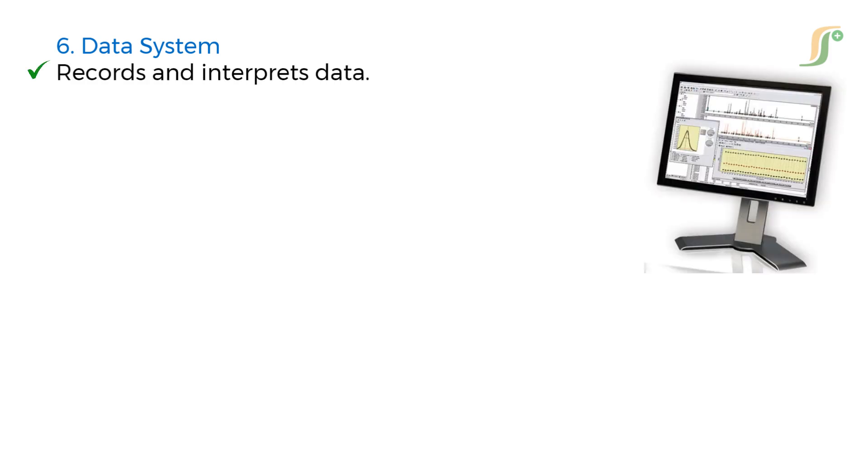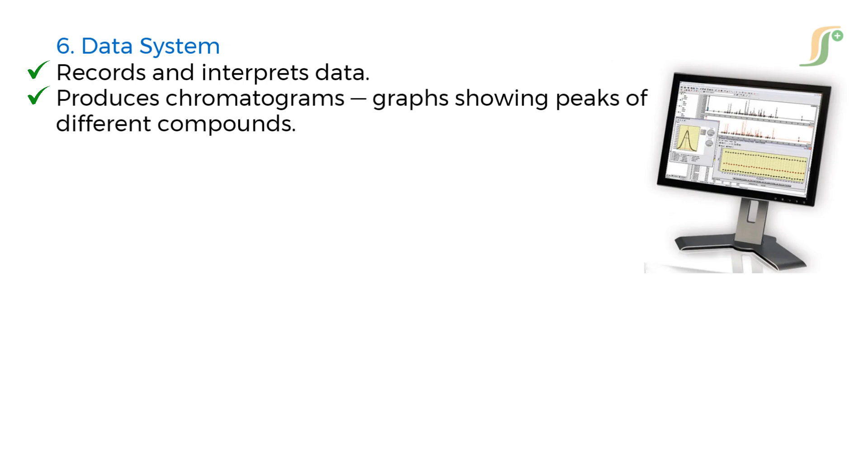Sixth component is data system. It records and interprets data and produces chromatograms showing peaks of different compounds. Peak retention time is identification and peak area or height is quantification.